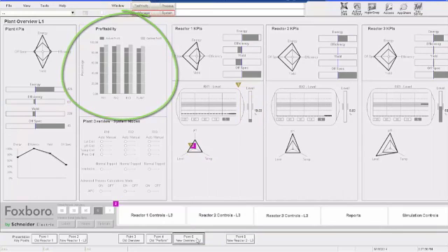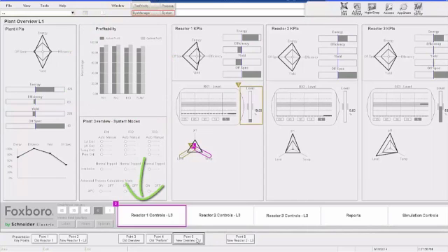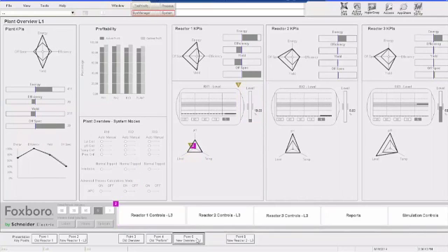In addition to that, the use of dashboards with intelligent alarm propagation can help operators avoid common mistakes. Human error can be a major contributor to industrial accidents, and a major cause of human error comes from when an operator is so hyper-focused on one problem, he doesn't realize a higher priority issue needs his attention. One benefit of situational awareness graphics is good use of the pop-out effect. Color as a metric is used sparingly, so when it is used, it pops right out at the operator, so he knows something is wrong.